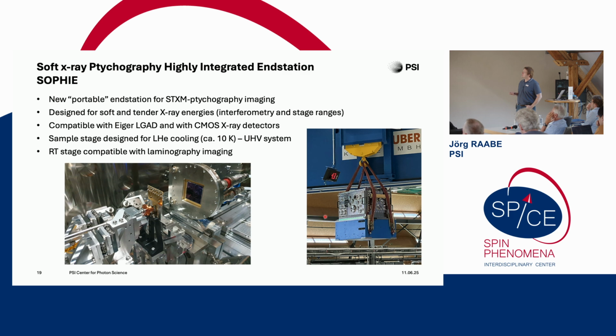And perhaps one important thing, especially in ptychography, is that detectors are always an important part. In hard X-ray, we typically have these single photon counting detectors, and we have the detector group at PSI, which is really a big advantage. They did some further development so that you can use the single photon counting detectors with special sensor chips also with soft X-rays. So we brought the limit, which is typically at, let's say, 2 keV, down to below 500 eV.